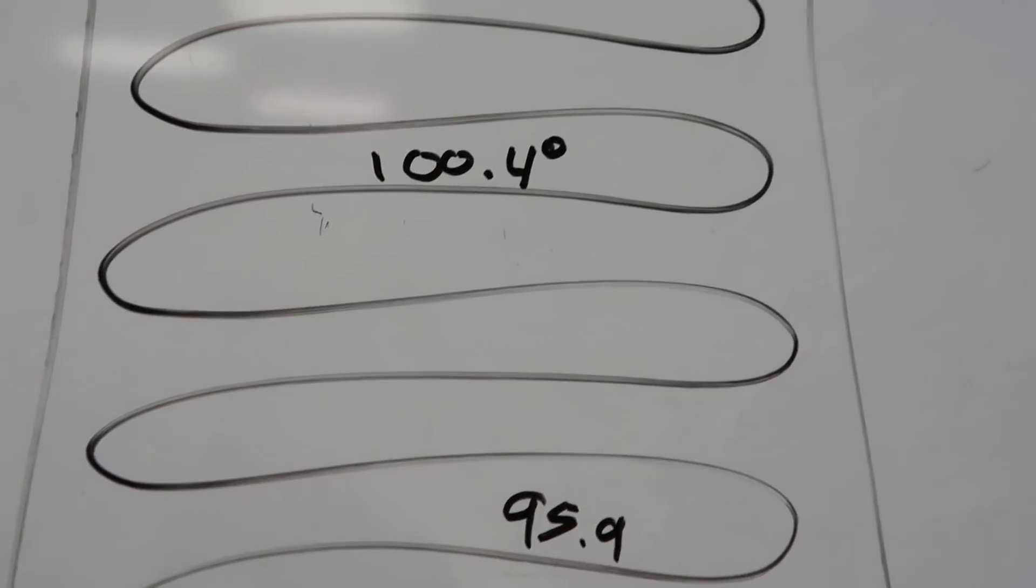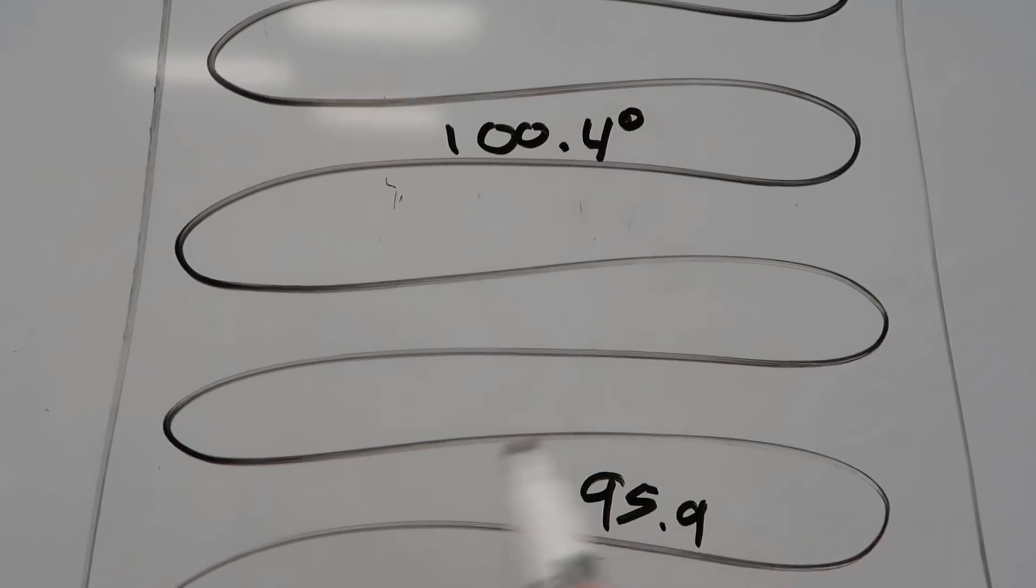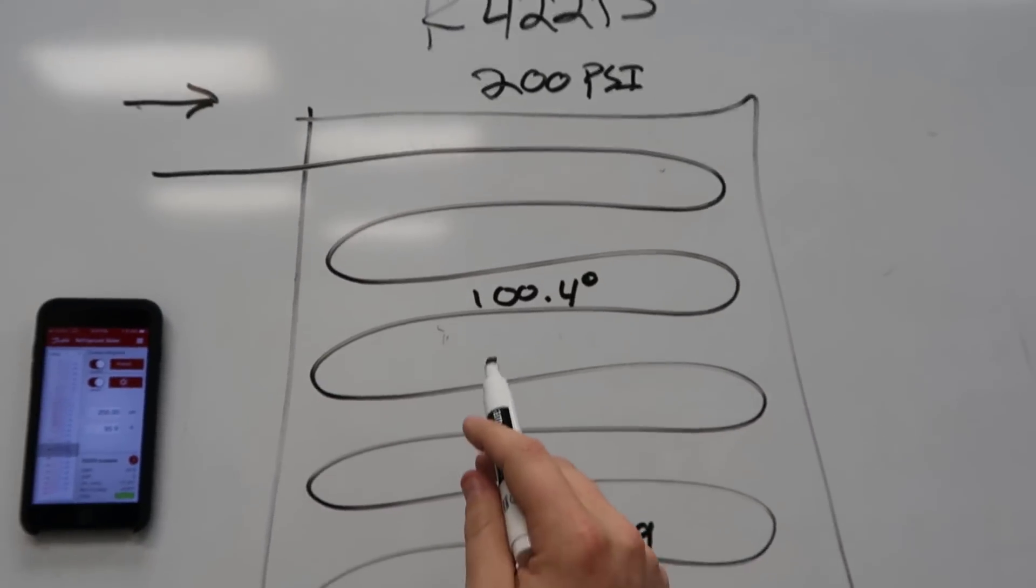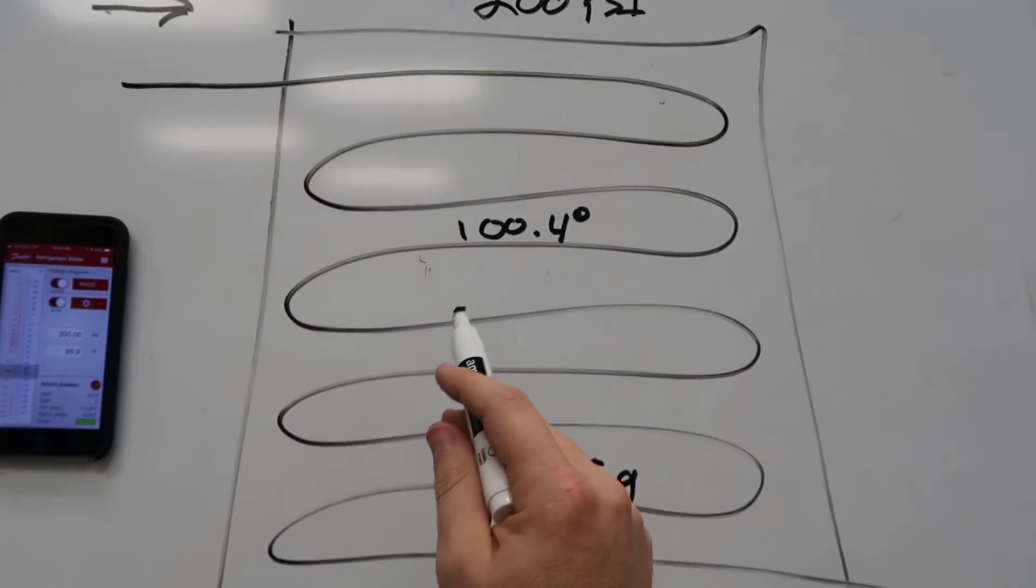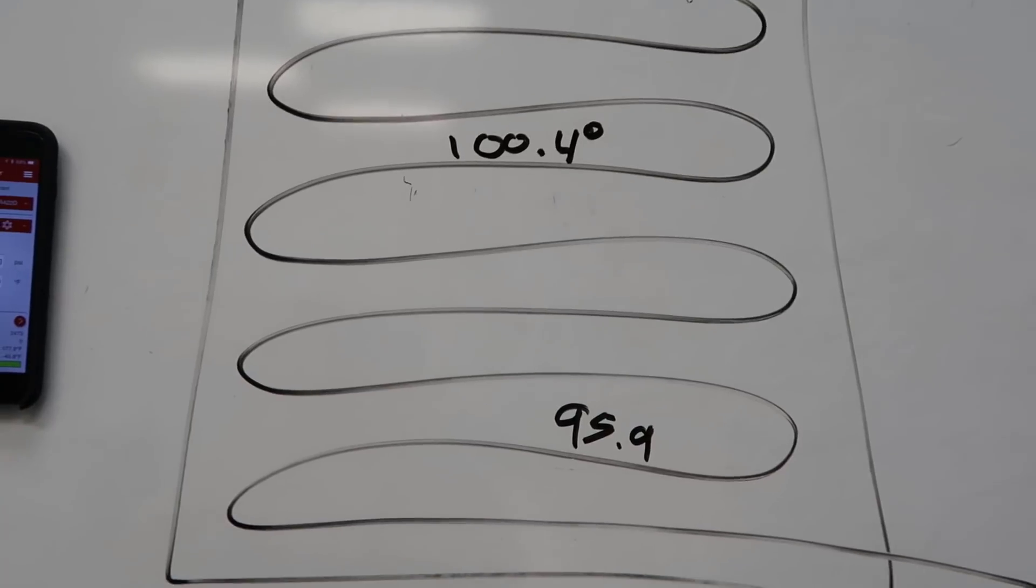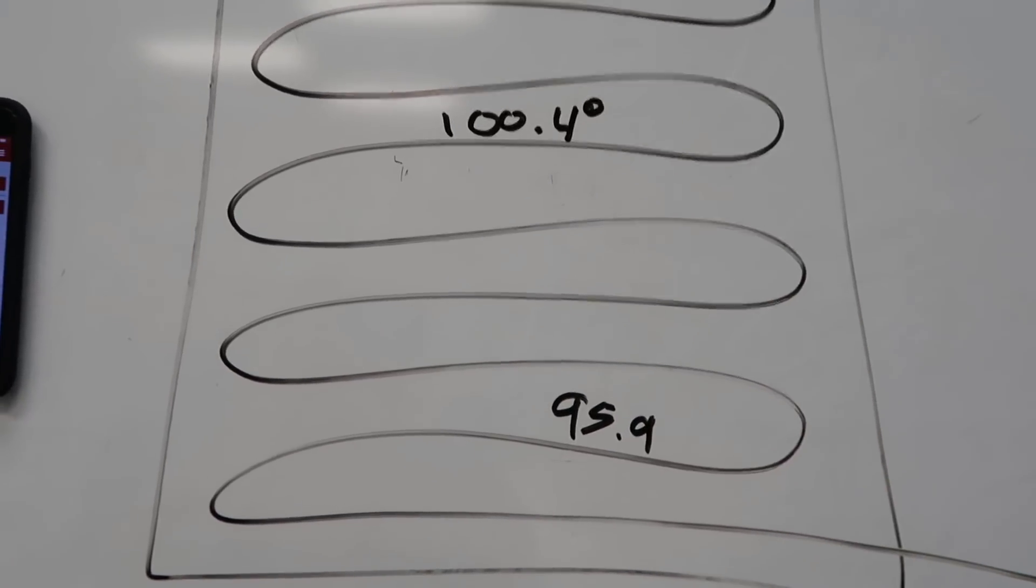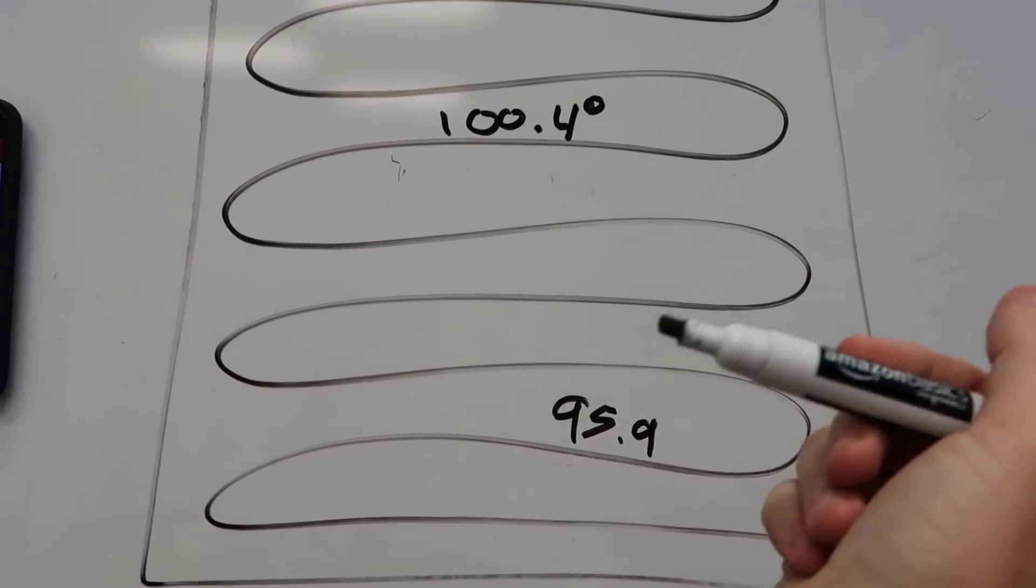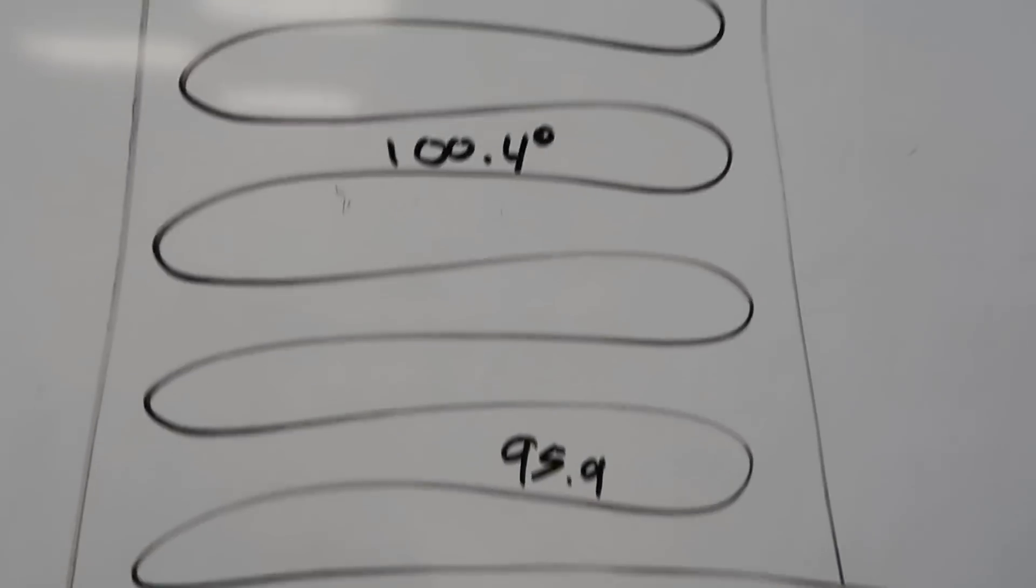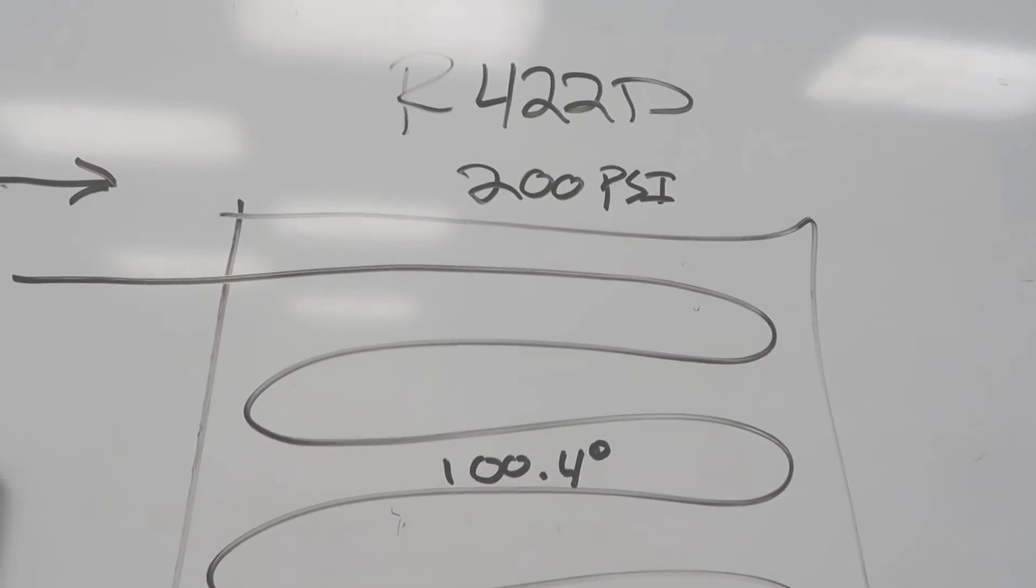So there you have it. That is glide in action. And then if we're actually looking at the temperature, if we want to say what is the temperature of this condenser coil, we would have to take an average of these two. But for calculating subcool, we would use the lower number, which is the bubble. Hopefully that's helpful. So I'm Brian Orr with HVAC School and HVACrSchool.com. Thanks for watching.